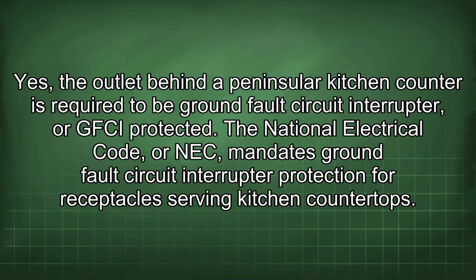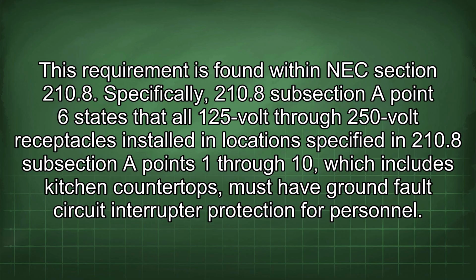Yes, the outlet behind a Peninsular kitchen counter is required to be ground fault circuit interrupter, or GFCI, protected. The National Electrical Code, or NEC, mandates ground fault circuit interrupter protection for receptacles serving kitchen countertops. This requirement is found within NEC Section 210.8. Specifically, 210.8 subsection A.6 states that all 125V through 250V receptacles installed in locations specified in 210.8 subsection A.1 through 10, which includes kitchen countertops, must have ground fault circuit interrupter protection for personnel.